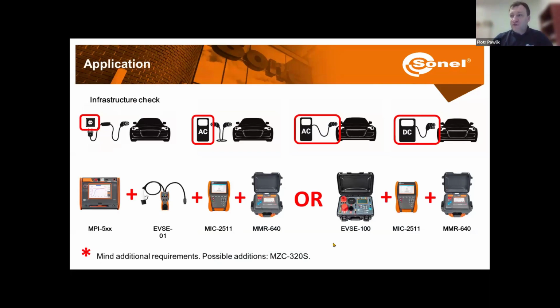And for that reason, we are going to need a set of meters: the multifunction meter with EVSE-01 adapter, a micro-ohmmeter with a test current of at least 10 amps to check continuity, and for checking SPDs, an insulation resistance meter which has such capability. Or we can use the EVSE 100, again together with a meter for checking SPDs in the DC charging stations, and the micro-ohmmeter for checking continuity.